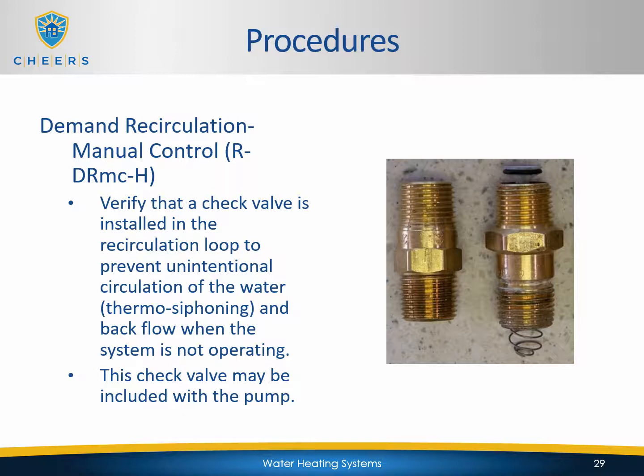You will then verify that a check valve is installed in the recirculation loop to prevent unintentional circulation of the water, also called thermosiphoning, and backflow when the system is not operating. This check valve may be included with the pump.